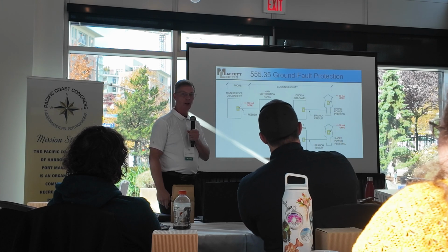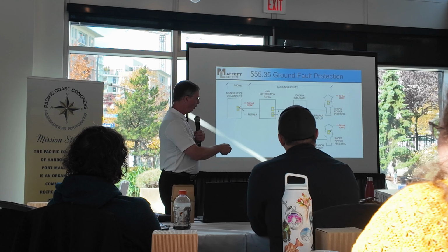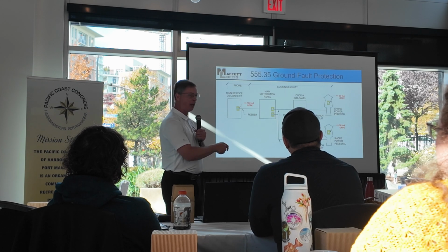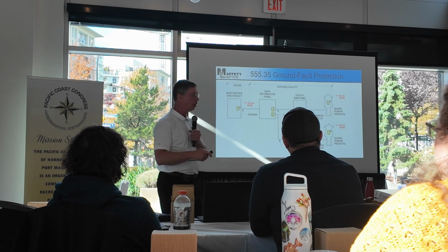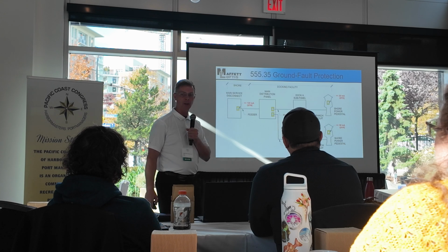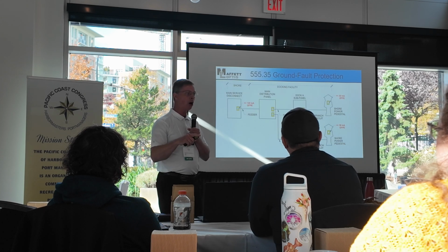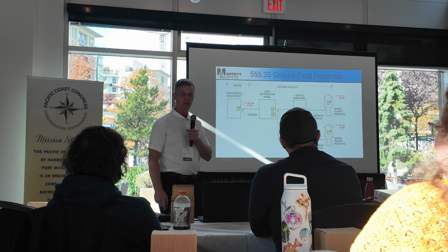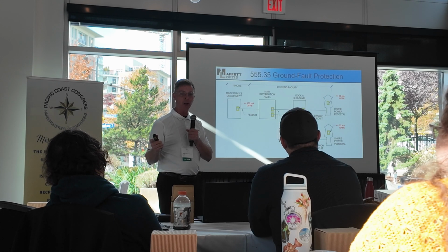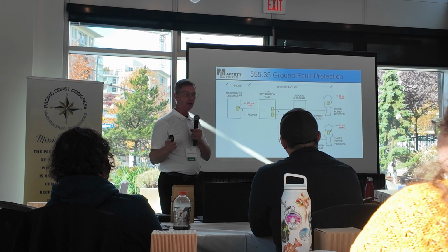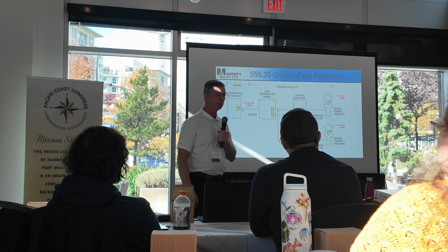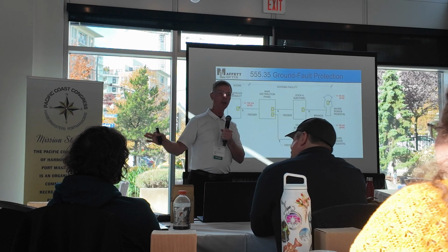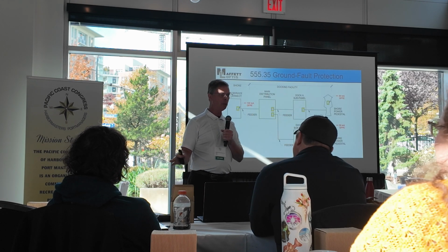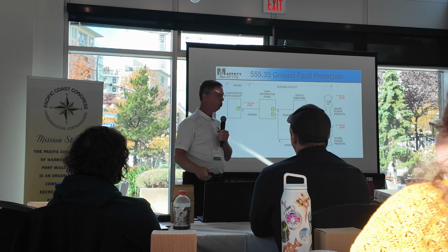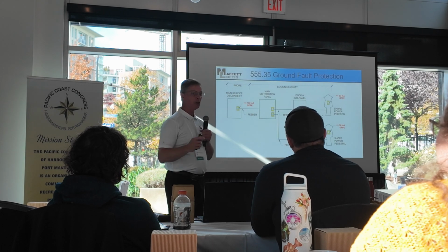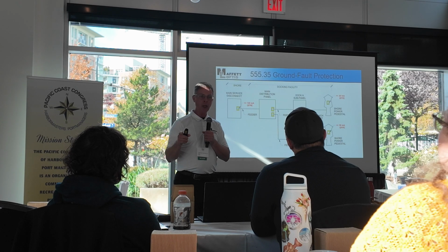I mean, ideally, point of use. Ideally, it'd be local, right? Because then it would only affect that one boat, and that's what the idea is. If it trips up here, what is it going to affect? The whole marina. All of them. Now, how many calls are you going to get if it trips all of them? You're going to get a lot of mad people calling you because their power tripped out. Not only that, you won't know what boat it is, because it could be any boat in the entire harbor that trips the GFPE. You don't know which boat it is. So you always want it to trip locally. So this coordination is extremely important.